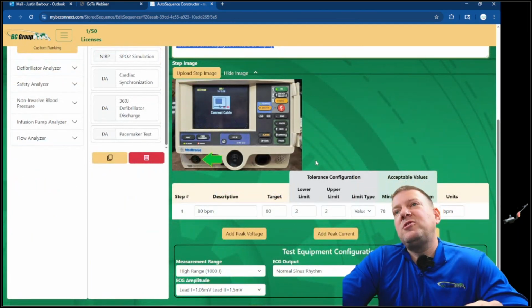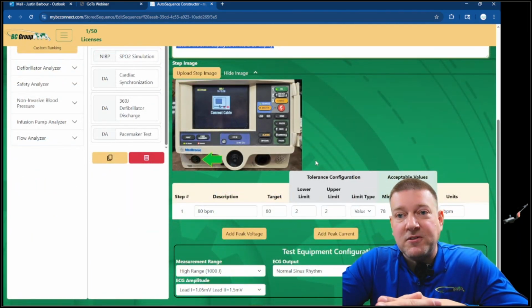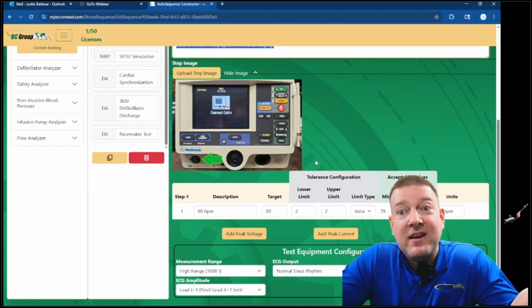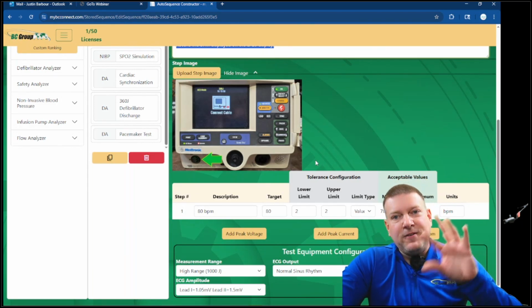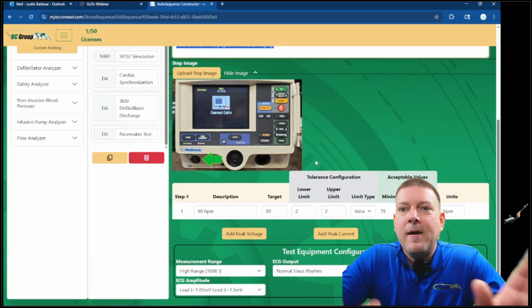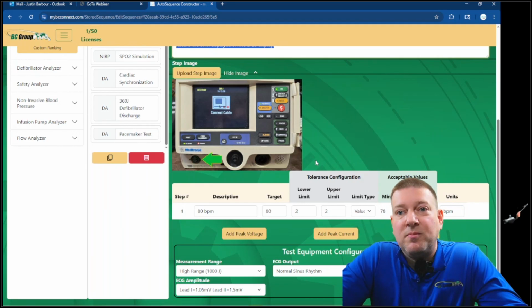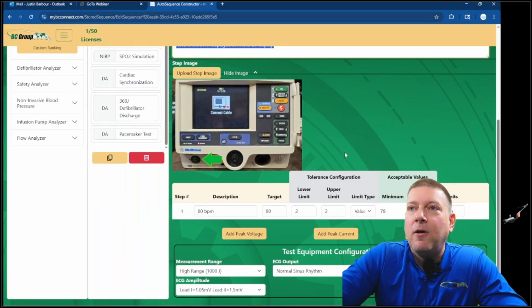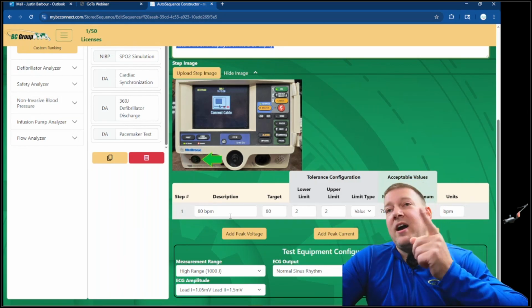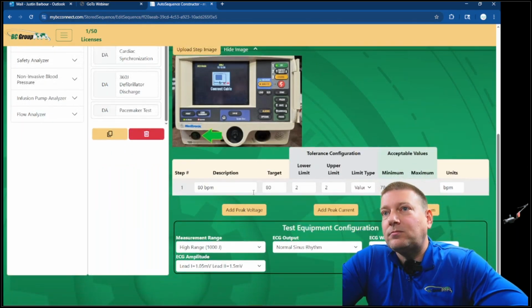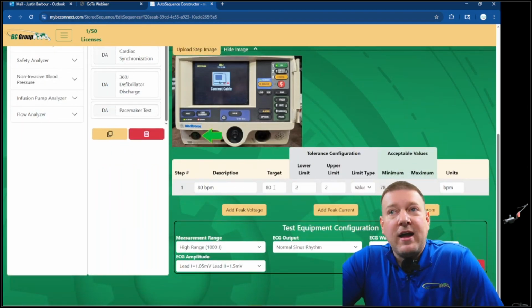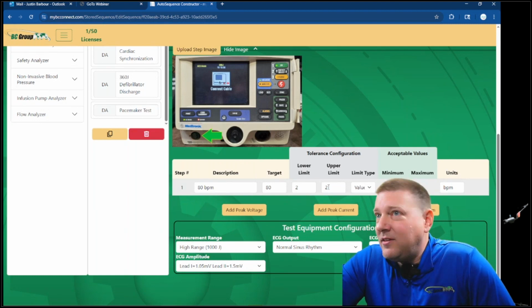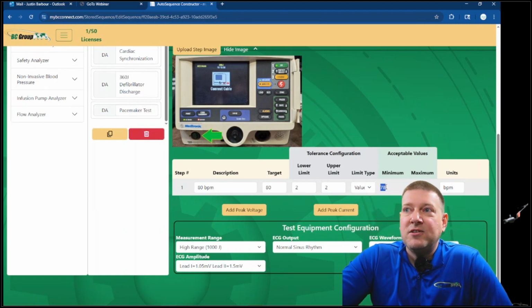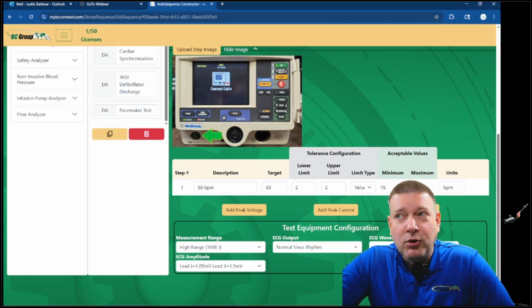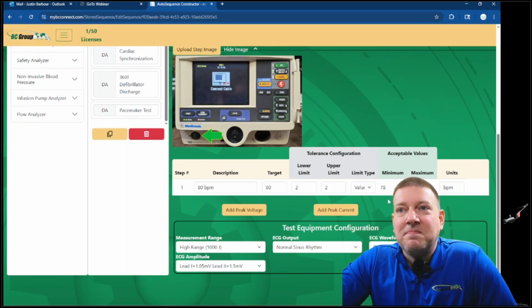So this is one of those steps where they're going to be typing in some results, because BPM is not something any analyzer can detect. So they have to visually go over to the device under test, match up, make sure that it has a certain BPM, type in what they read, what they verified, and it will give them a pass or fail. So down here, you can see where I set the pass or fail values. So 80 BPM, I have a target of 80. I set the upper limit, the lower limit, and over here, as long as it's between 78 and 82 BPM, they'll get a pass condition.